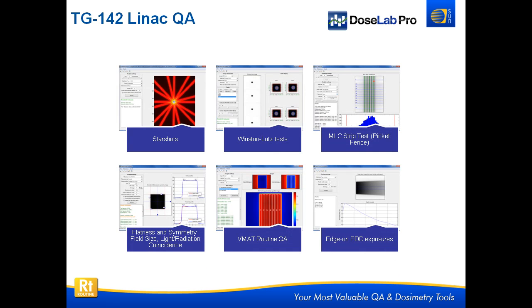The Linac QA components we have in DoseLab are Starshots, Winston-Lutz tests, MLC Strip Test, the picket fence test, flatness and symmetry — which includes full field size and light radiation field coincidence — VMAT routine QA, and edge-on PDD exposures. What's nice about these is that they're all fully automatic. Except Starshots, you have to click twice there; everything else is basically zero click. You load the image, click go, and it gives you your results, tells you if anything failed your tolerances, and then allows you to save a report to the database extremely quickly.